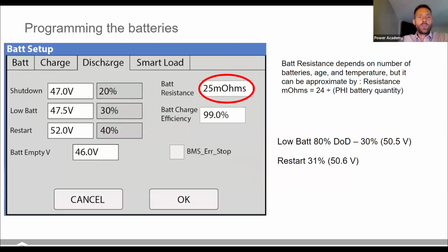On the discharge side of things, the low battery is the percentage or the voltage at which the battery will start beeping at you. The inverter will start beeping to let you know, hey, you're getting low on battery. You can turn the beep off if you want, but that's just to trigger that signal that you're getting low on battery. So it'll send that to the app, and that'll send you a notification. The shutdown voltage or percentage is the percentage at which it turns the loads port off.